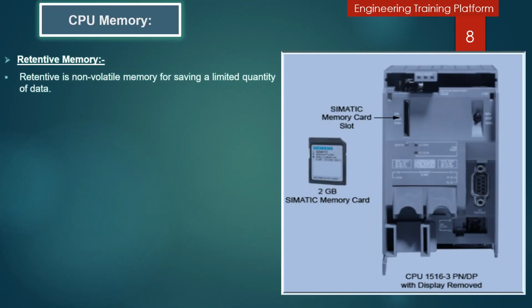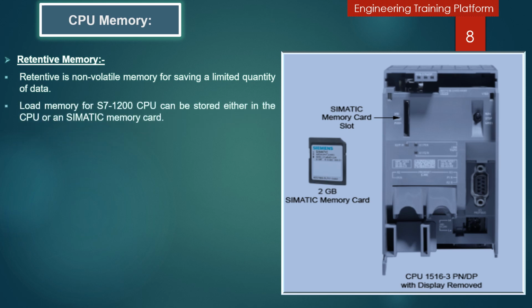Now we will discuss the retentive memory. Retentive memory is non-volatile memory for saving a limited quantity of data. Load memory for the S7-1200 CPU can be stored either in the CPU or in a Simatic memory card. Retentive means the component will not forget its value when the system restarts.